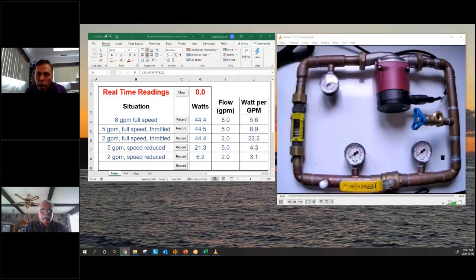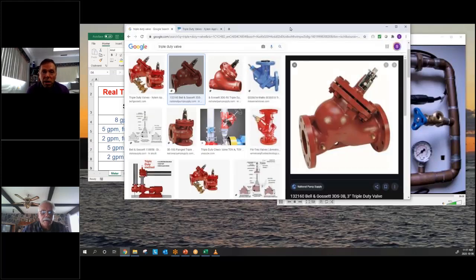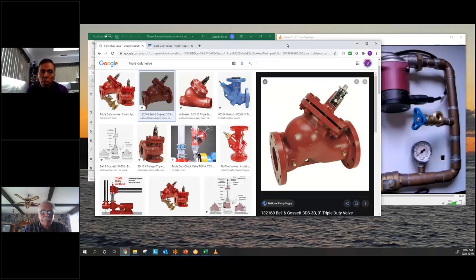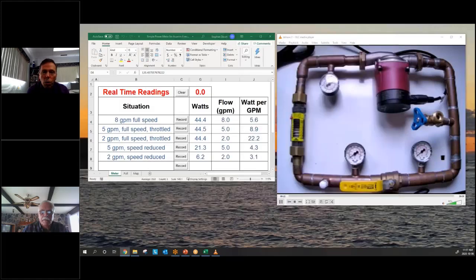Otherwise, you may actually burn out your motor, because sometimes by opening the valve, you have more flow, which can, depending on the pump, create more power and overheat your motor. So the triple duty valve is something you have to keep an eye on. And then you get your circuit balancing valve. If all your circuits are partially closed, that means one should be open and the other one partially closed. So you always have to be careful. As soon as you see a closed valve, that's an indicator to dig into that system.